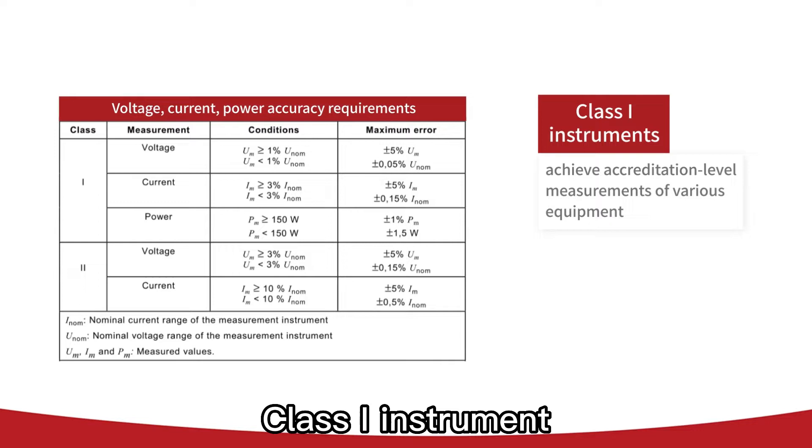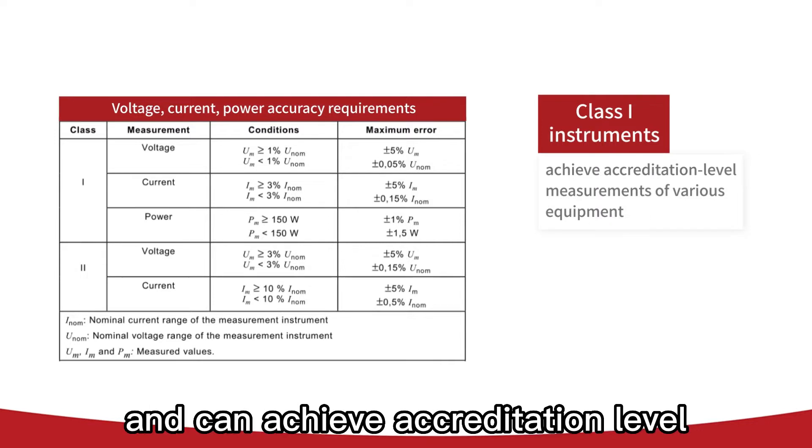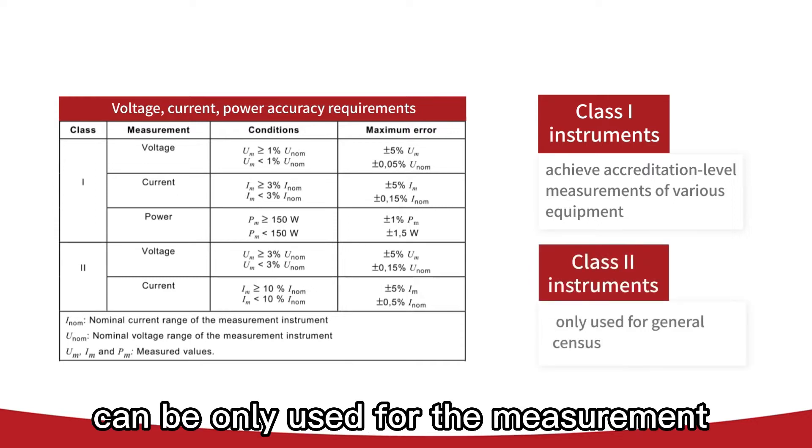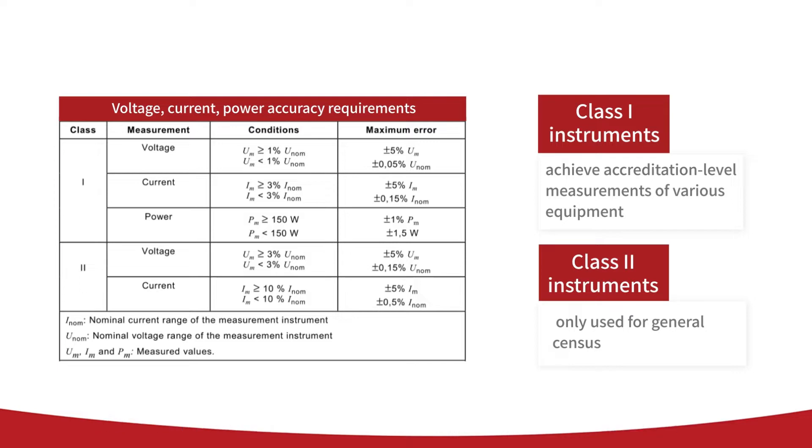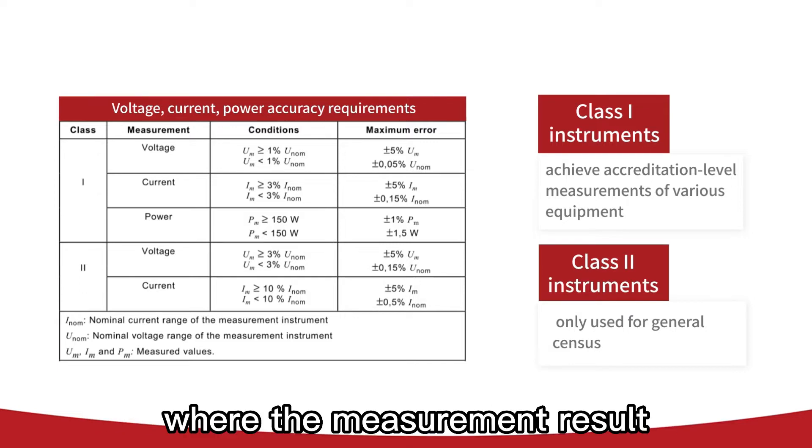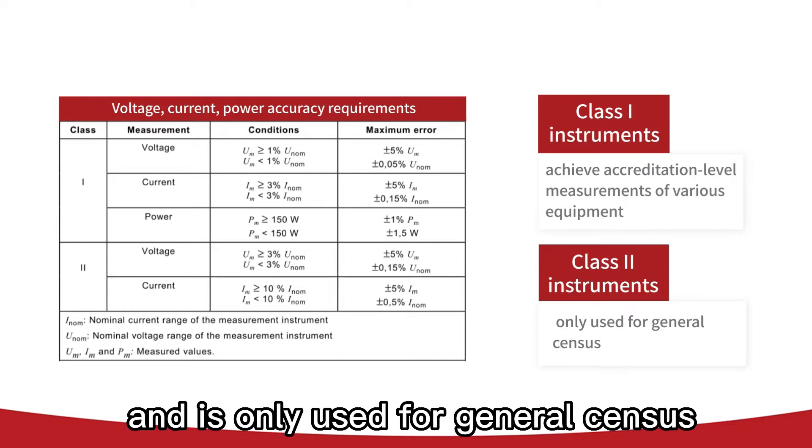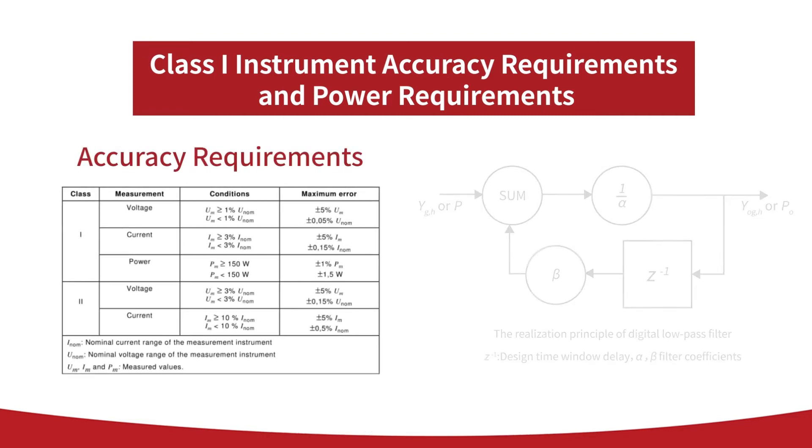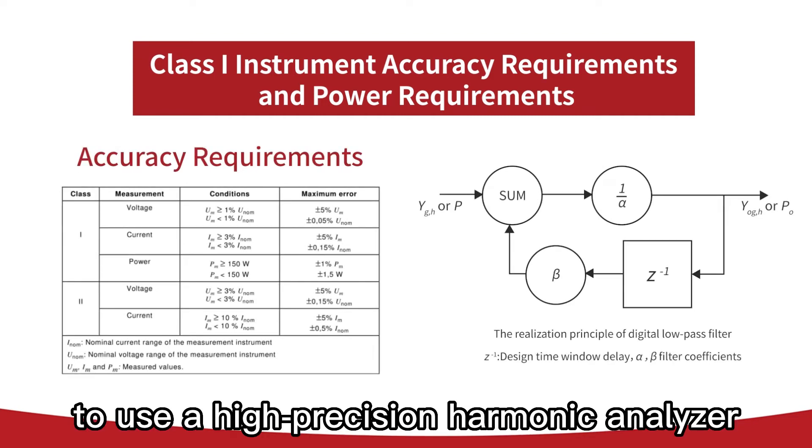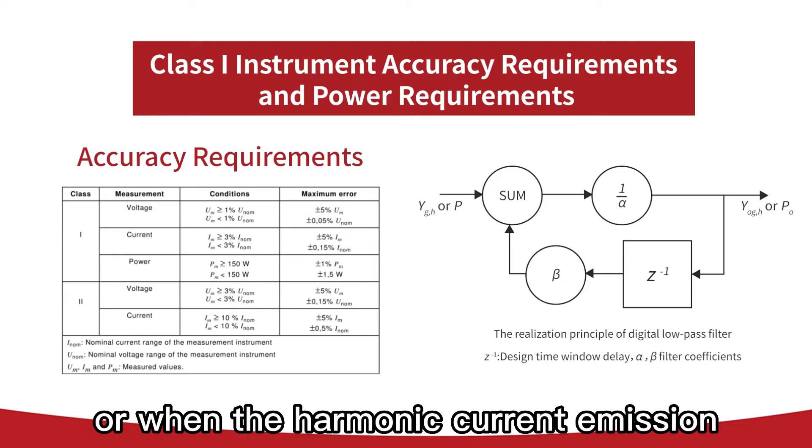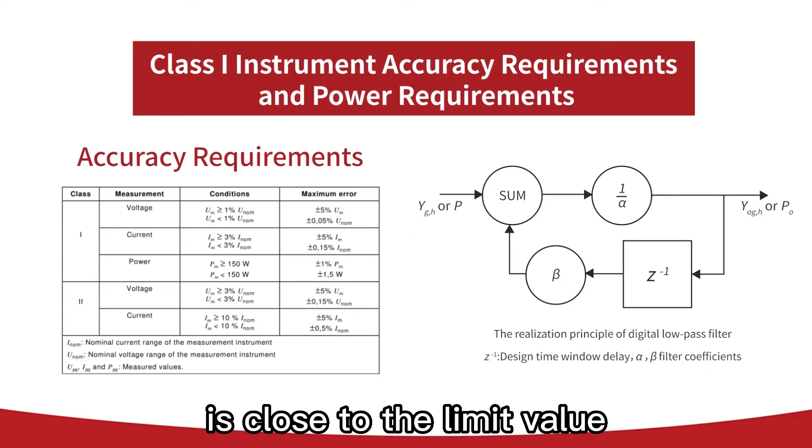Class I instruments have high measurement accuracy and can achieve accreditation-level measurements of various equipment. Class II instruments can only be used for the measurement of harmonic current emission where the measurement result obviously does not exceed the limit value and is only used for general census. Therefore, it is recommended to use a high-precision harmonic analyzer when performing accreditation tests or when harmonic current emission is close to the limit value.